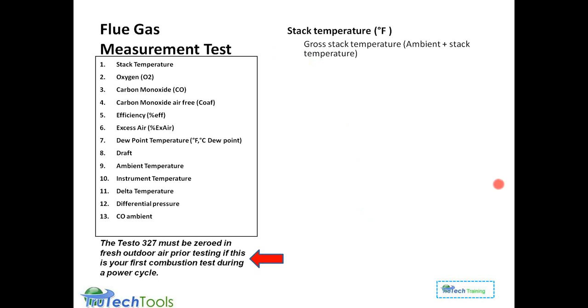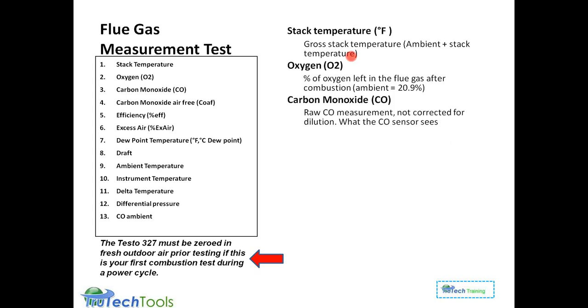Stack gas temperature, that's the gross stack temperature, which is the ambient temperature plus the net rise in the stack temperature. Oxygen is the percent of oxygen left in the flue gas after combustion. If you go back to the slide where we showed you how combustion works, and you have incomplete combustion, which is normal in the world, and you have that oxygen on the other side of the equation, that's the excess air that came through. That actually is a little hint to what's going on in combustion, so that's a look-see into the combustion. Oxygen is a measured parameter that's used in a couple of different calculations for the meter.